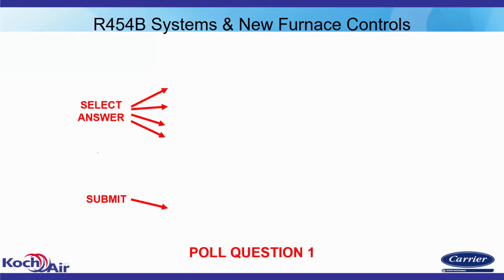All right. So let's look at the results here. About 75% of you said 228 square feet. And a few of you said 1,000, 2,500, 3,500. So what we were looking for here, the correct answer was 228. And I probably should have worded the question a little differently, where it said that is the minimum. So what is the minimum square feet that we need to dissipate 15 pounds of refrigerant?